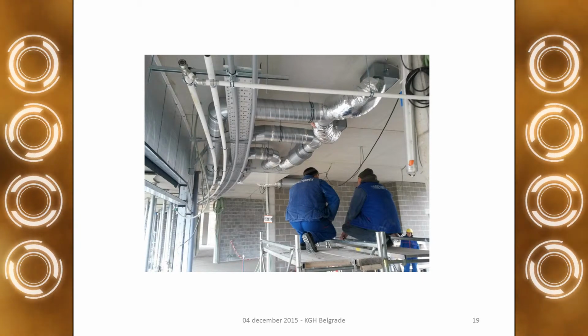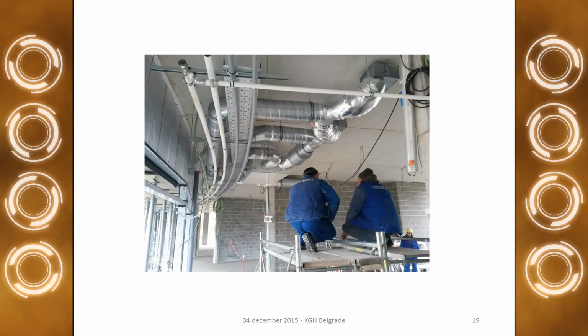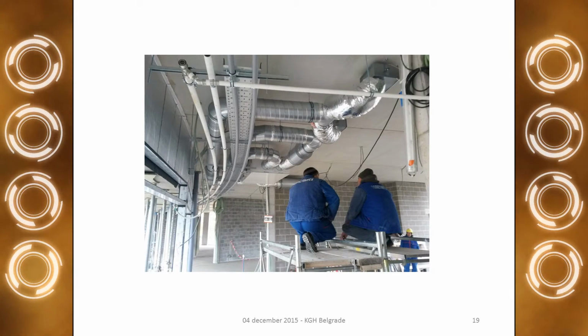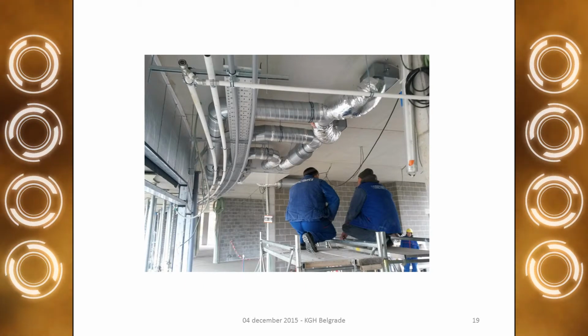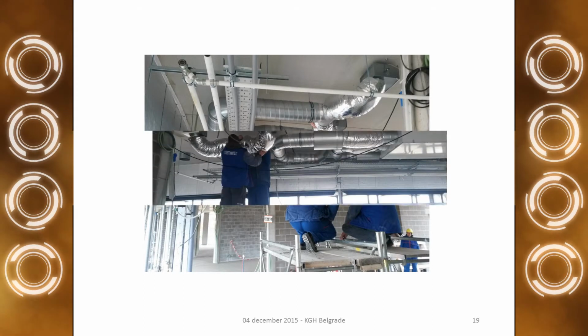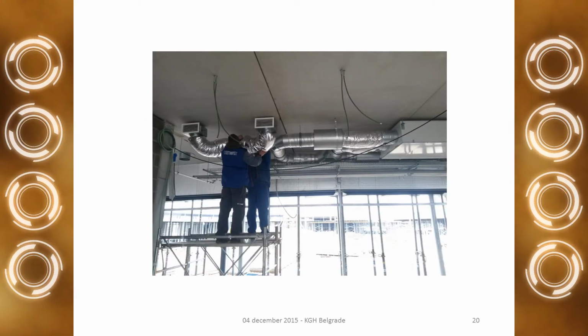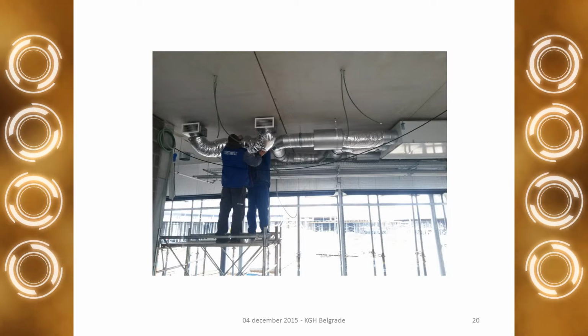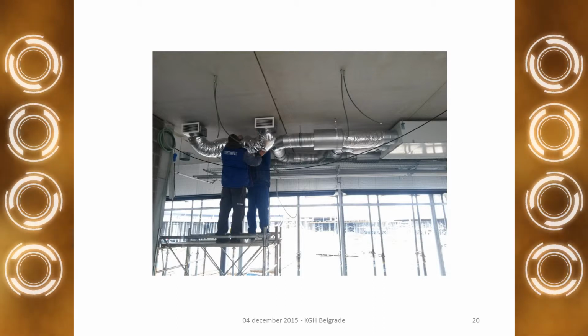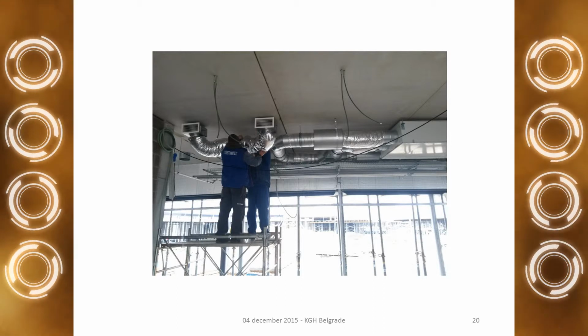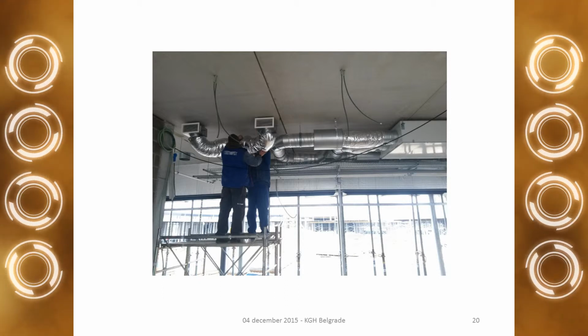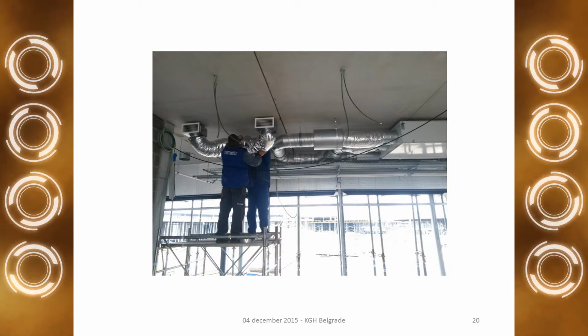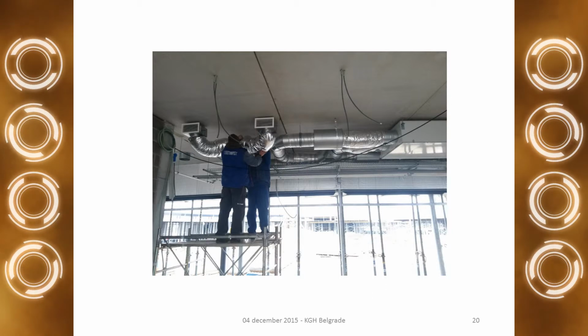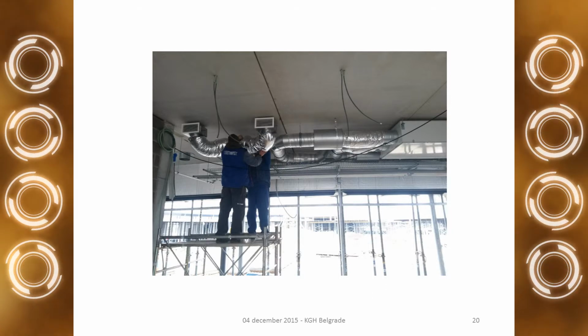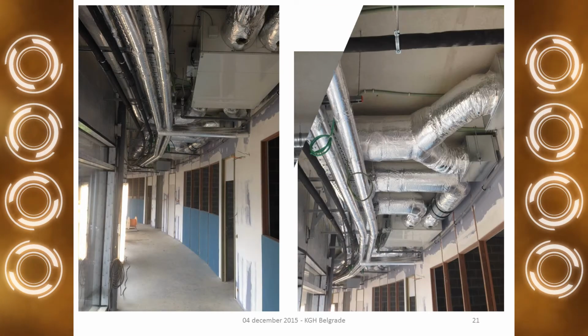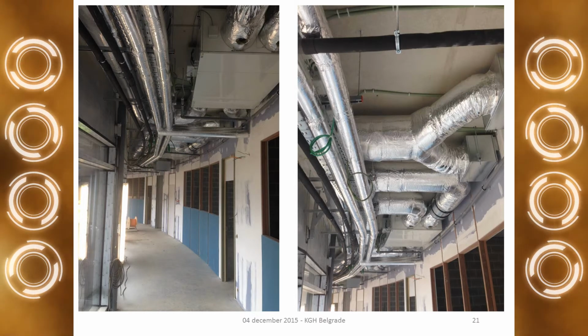An important thing was also the noise characteristic, and taking into account the noise value, we made the calculation for the noise to calculate the sound dampers for each air handling unit, having in the end in the classroom 35 decibels of noise, which was requested and is according to the standard 15251.